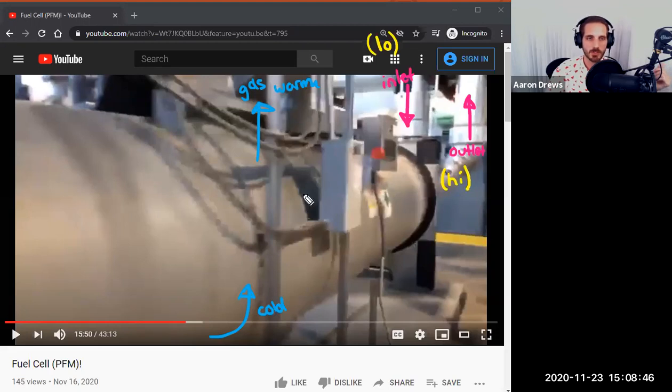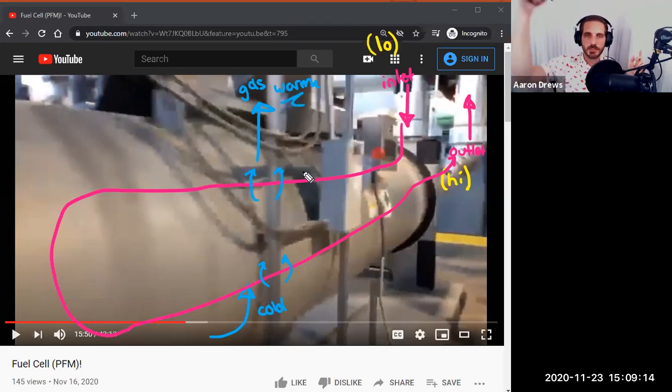And so this water is running through another series of tubes, right? It comes in through here, runs way down our evaporator, loops back around until it eventually leaves. And our refrigerant, which is the thing that is doing the cooling, starts off cold, flows over the outside of these tubes, and energy is transferred from the warm water coming in to this refrigerant. So the refrigerant gets a little bit warmer up here. And then it hits that compressor, turns around and enters the condenser on the other side, right?